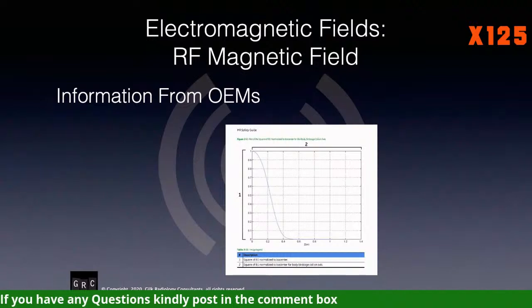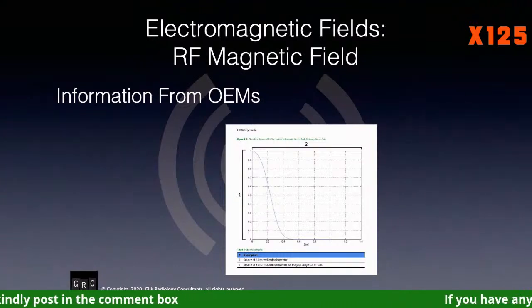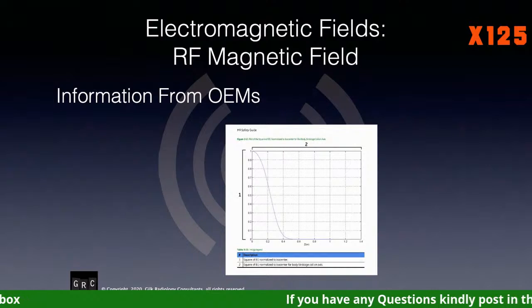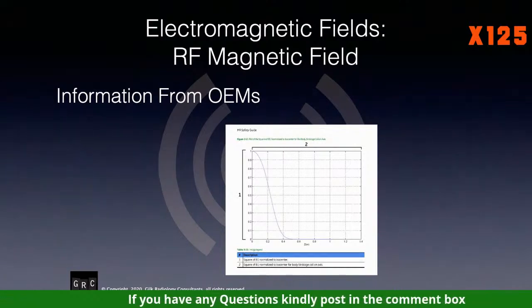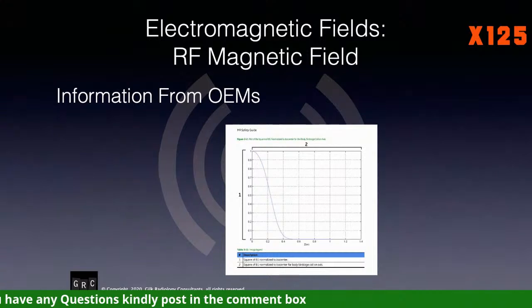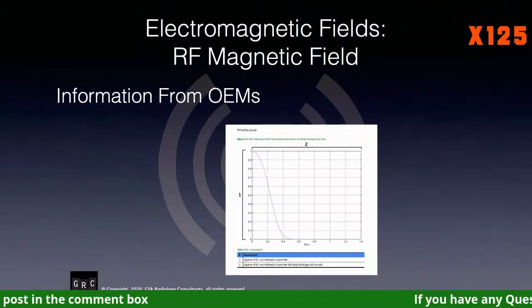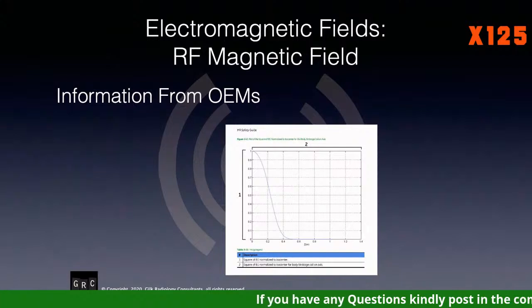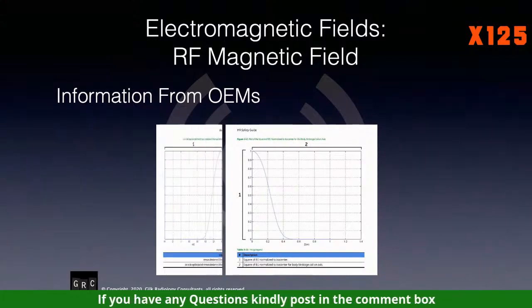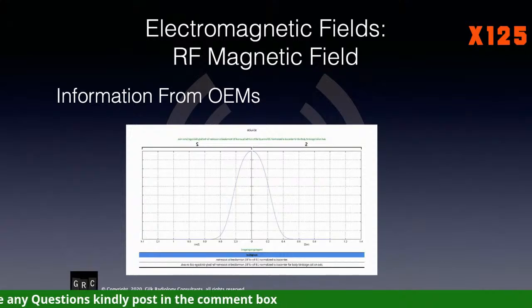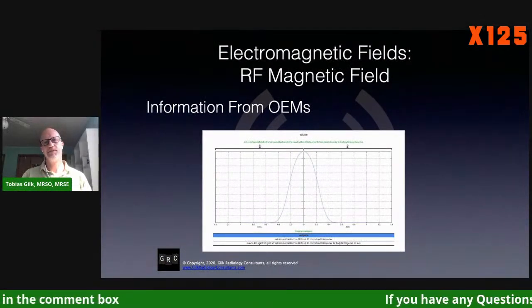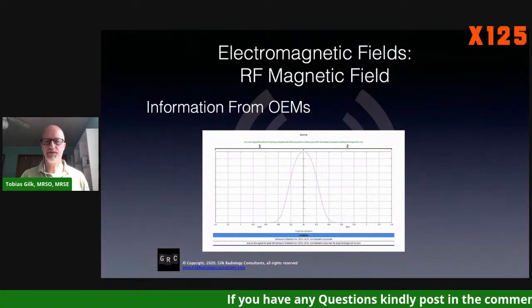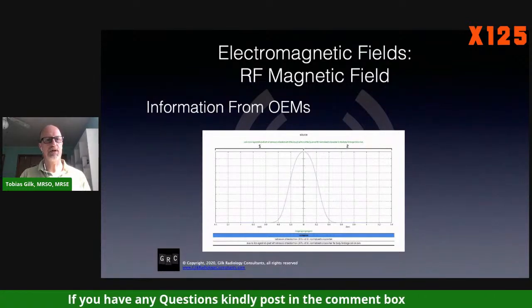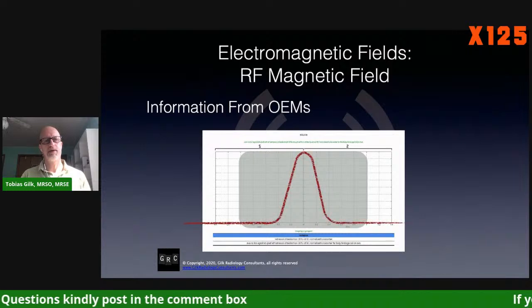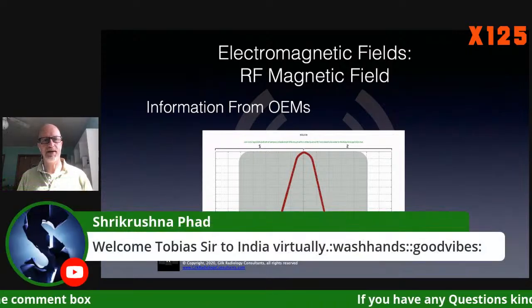Unfortunately, not very much. This particular example is from GE. Like the time-varying gradient spatial distribution information from the vendor, this only shows half of a distribution curve. I didn't do it on the previous one, but imagine this happening to the time-varying gradient information also. If we show what happens in both halves of the bore, and that's actually difficult to see, I'm going to overdraw the curve, and then the gray shaded area is the length of the bore.